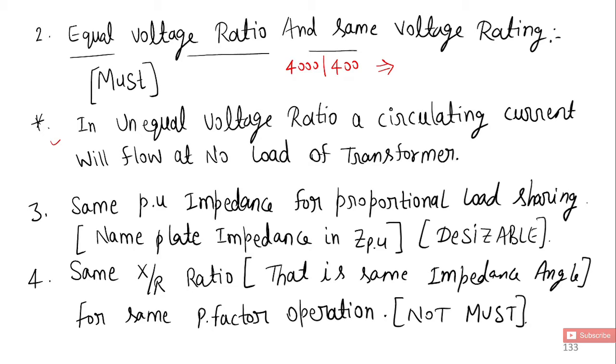In unequal voltage ratio, circulating current will flow at no-load of the transformer. If this is not same for both transformers, there will be circulating current at the load side and this will reflect at primary side also, so you can't connect with different voltage ratio.